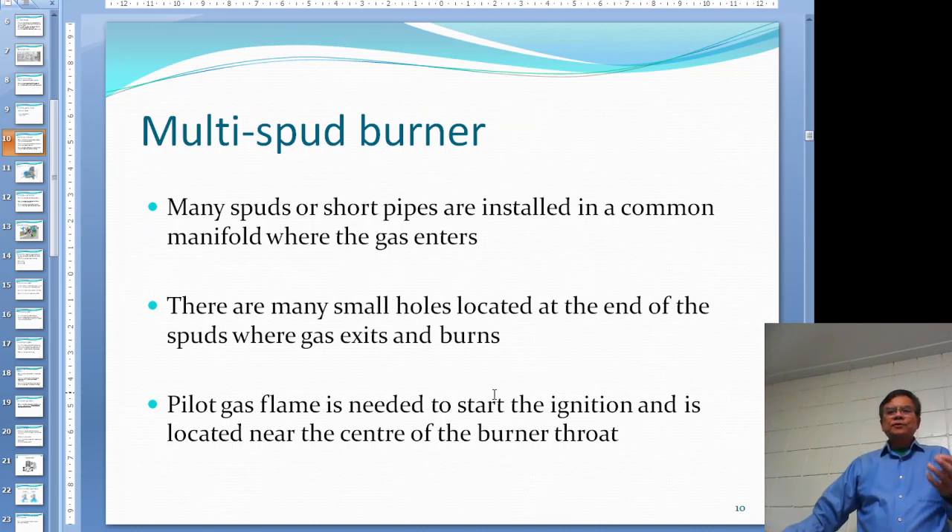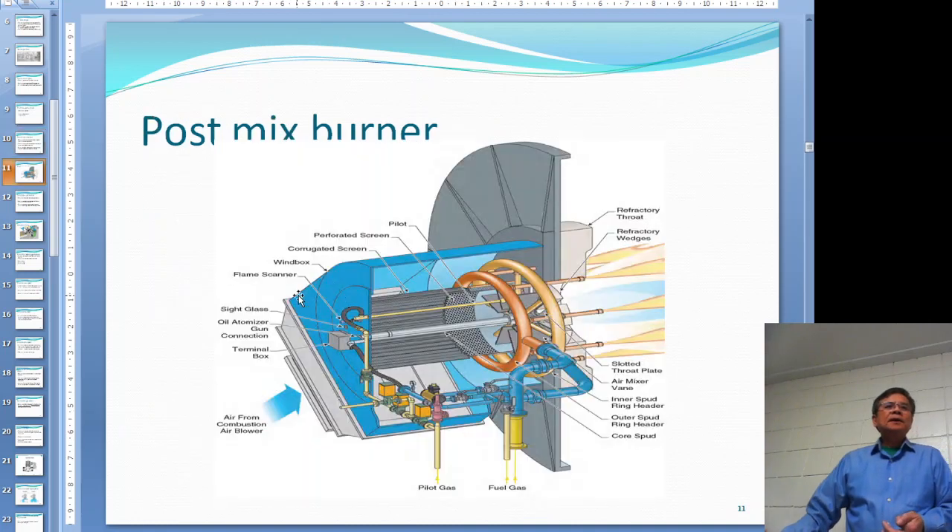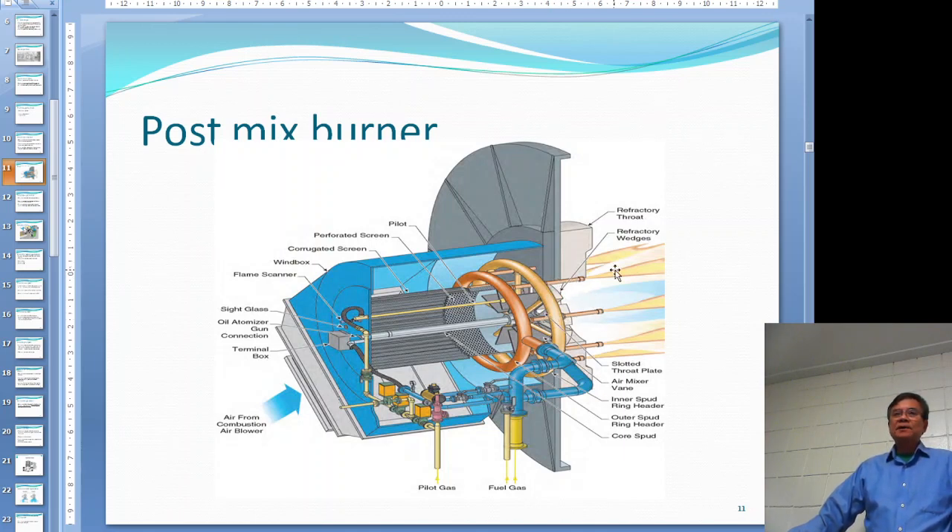For most big boilers you need to establish a pilot flame to start ignition. Looking at the post-mix burner, you can see the large ring - that is the manifold - and on the manifold there are small pipes sticking out where the gas comes out. The primary air comes in through one inlet, and the secondary air comes in through the louvers. The gas enters the manifold, comes out through the spuds, and burns in front of there.